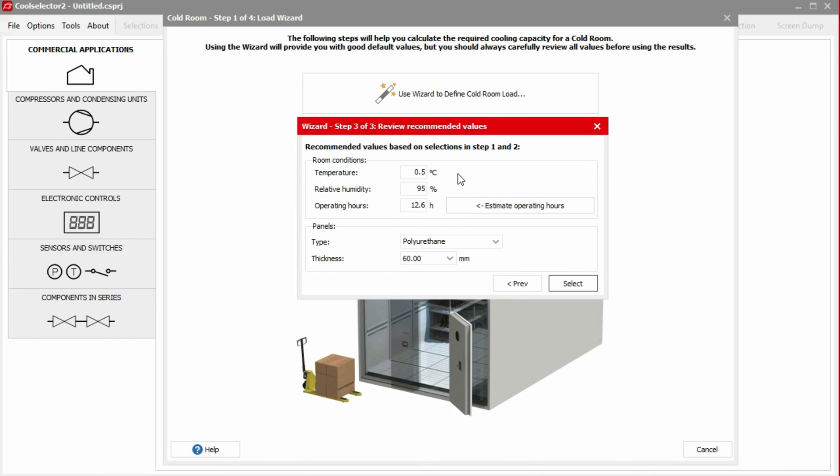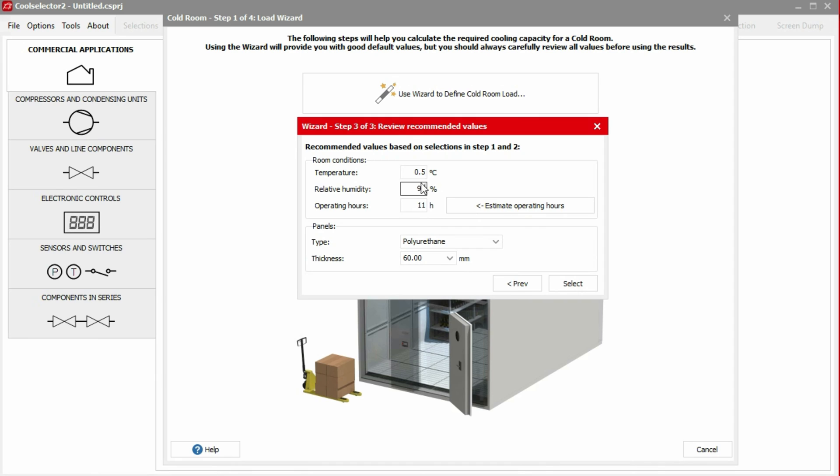Now we choose which humidity level we require inside. This will impact the run hours to keep the relative humidity in the cold room. If we change this to, for example, 98% relative humidity, then click the Estimate button, the value changes to 11 hours per day. We'll stick with 95% for this example and click Estimate again to update the run hours.